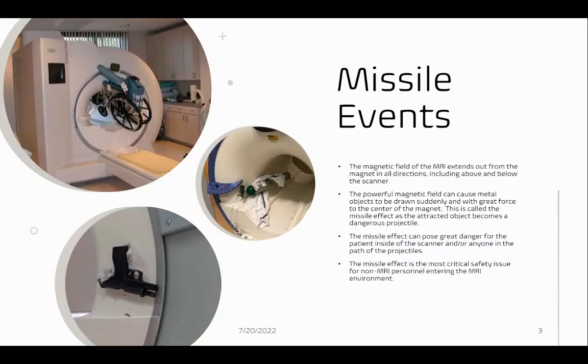Missile events are the most critical safety issue for non-MRI personnel entering the MRI environment. The magnetic field of the MRI extends out from the magnet in all directions, and if a metal object is introduced into the MRI suite or room, it will be drawn suddenly and with great force to the center of the magnet. This is called a missile effect, as the attracted object becomes a dangerous projectile. This effect can pose great danger for the patient inside of the scanner as well as anyone within the path of the projectile.